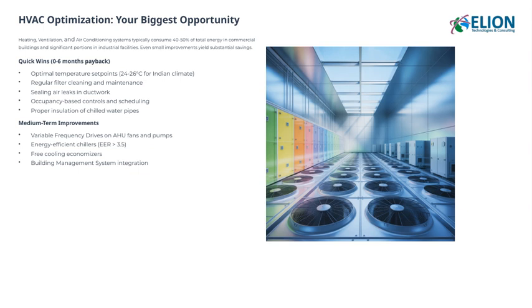In the short term, there are some quick wins you can implement within 6 months, such as setting optimal temperature ranges, around 24 to 26 degrees Celsius for the Indian climate, regularly cleaning and maintaining filters, sealing air leaks in ductwork, and using occupancy-based controls and scheduling to avoid unnecessary cooling when spaces are unoccupied. Properly insulating chilled water pipes also plays a key role in reducing energy waste.